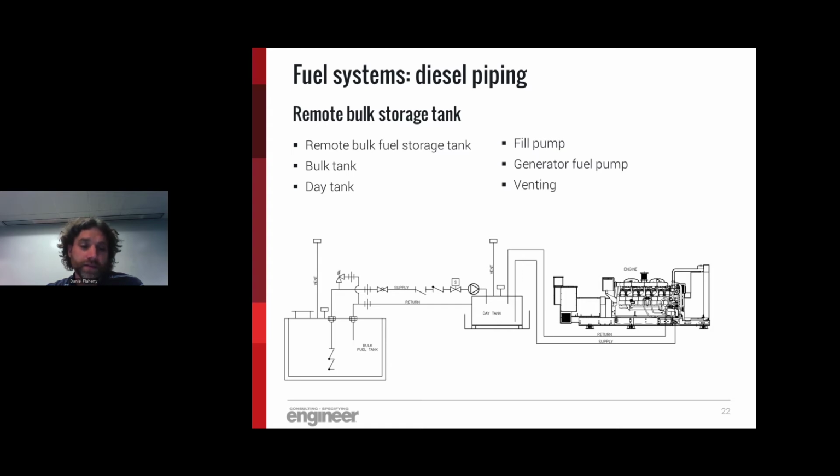And bear in mind that, due to the nature of all tanks being vented to atmosphere, these are all open systems. So you have to actually pull fuel from one side, and then your pump has to be able to push it through the system and return it to wherever it's going.